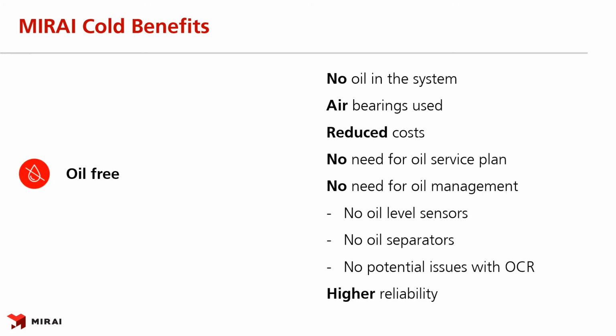One of the key benefits not mentioned so far is the oil-less design. We were able to design our machines with no need for oil due to the air-bearing design. This means reduced operating cost because there is no oil service plan required, and also reduced initial cost since oil management is not required at all. No need for oil level sensors, oil separators, and no potential oil circulation ratio issues. This all results in a much higher reliability.